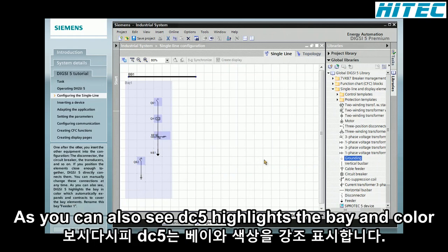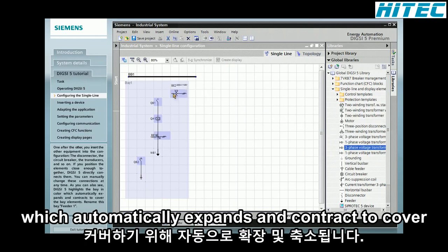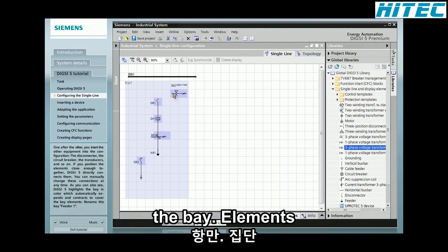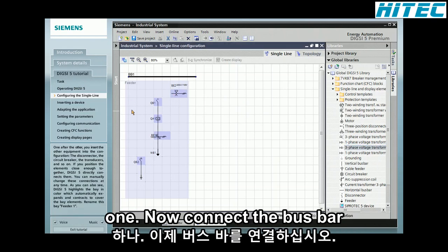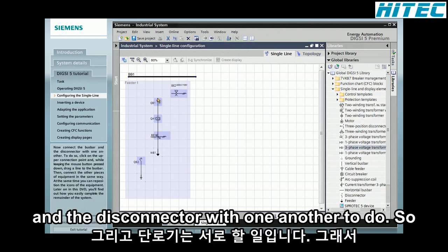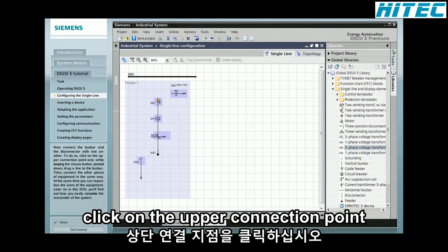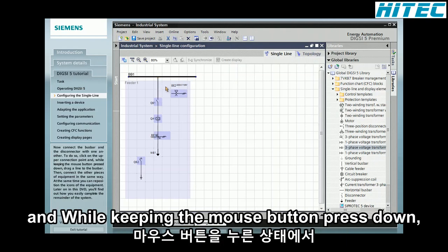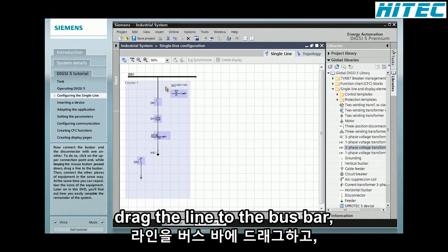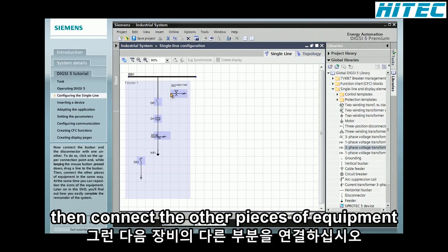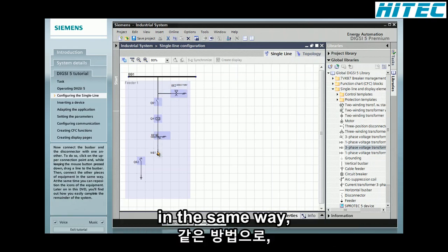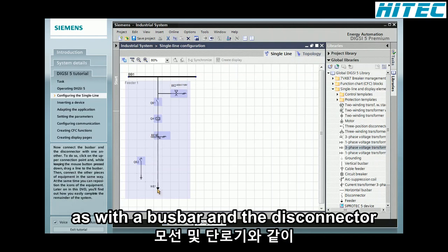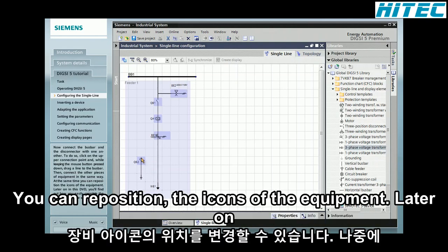As you can also see, DIGSI 5 highlights the bay in color, which automatically expands and contracts to cover the bay elements. Rename this bay Feeder 1. Now connect the busbar and the disconnector with one another. To do so, click on the upper connection point and, while keeping the mouse button pressed down, drag a line to the busbar. Then connect the other pieces of equipment in the same way as with the busbar and the disconnector. At the same time, you can reposition the icons of the equipment.